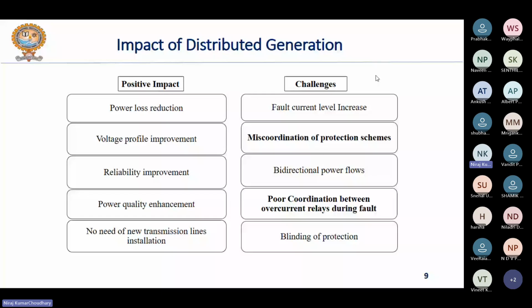limitations or issues may lead to a reduction in the reliability as well as the efficiency of the system, because you know that for any efficient protection scheme, there are certain key features that must be fulfilled, like speed of operation of the protective device, selectivity, and sensitivity. The least part of the affected system should be isolated from the remaining healthy system. So all these are the possible consequences that may arise due to the integration of DG in the system.